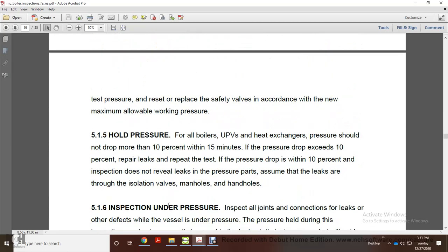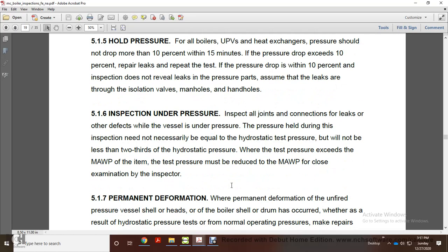5.1.5 Holding pressure for all boilers, UPVs and heat exchangers: the pressure must not drop more than 10% within 15 minutes. If the pressure drop exceeds 10%, repair the leaks and repeat the test. A pressure drop within 10% is acceptable if the inspection does not reveal leaks in the pressure parts, assuming the leaks are through isolation valves, manholes, or handholes.